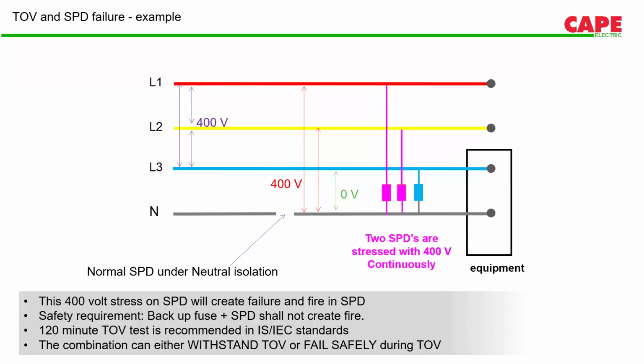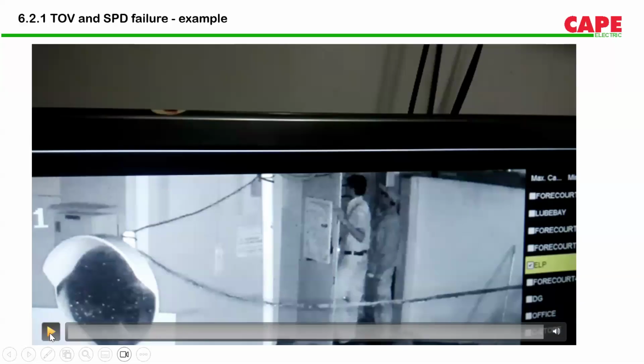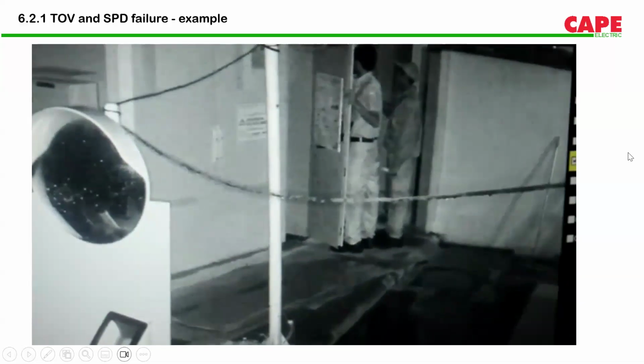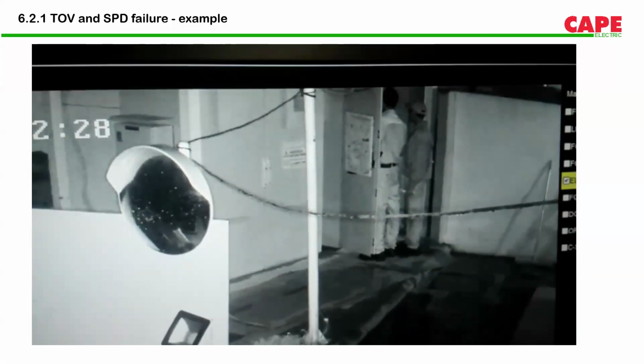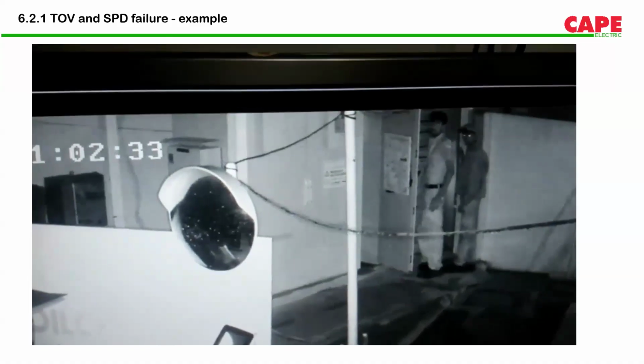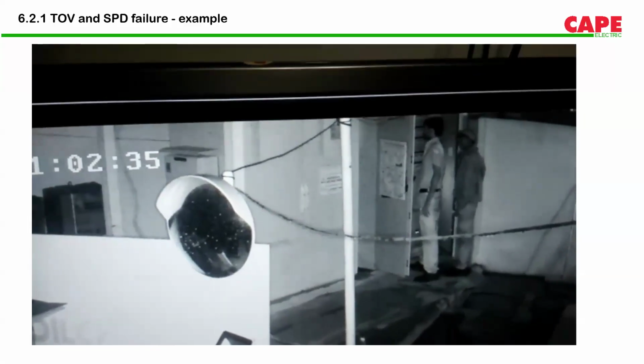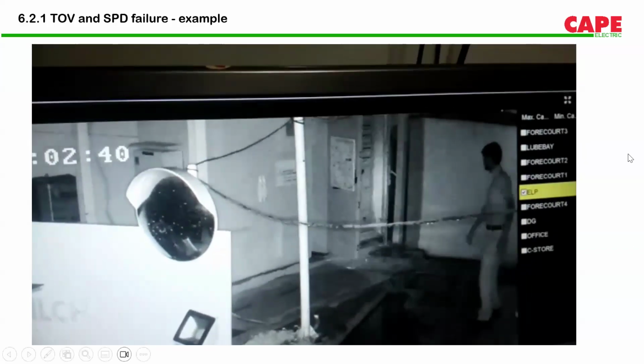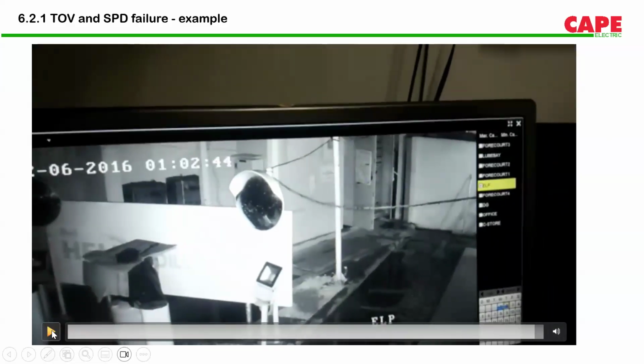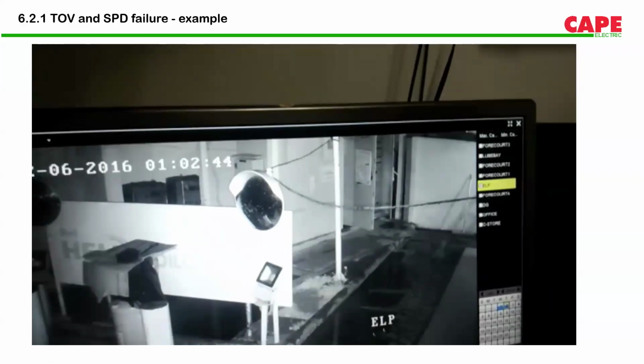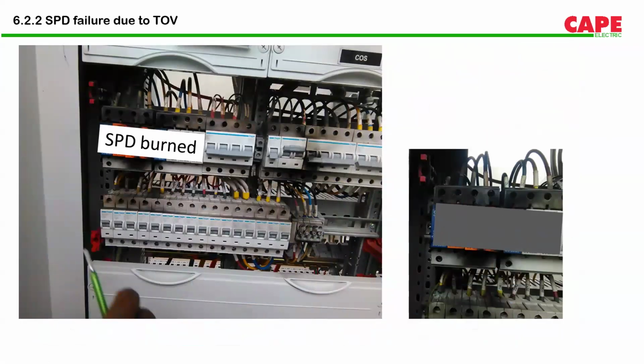This condition can fail an SPD, and I will just show you a small video of what can happen if the SPD is stressed under TOV conditions. This is a video from one of the places in Karnataka. This particular SPD was continuously stressed due to TOV conditions, and because of this extra 100 or 140 volts, the SPD blasted. This was the condition of the SPD once it failed.